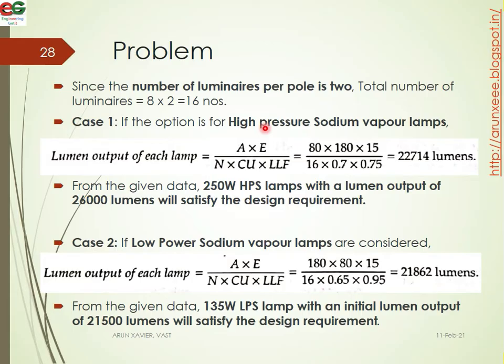The lamp output of each luminaire is calculated using the formula: A times E divided by N times CU. Using area 180 times 80 and illuminance value of 15, with 16 lamps, the required lumen output per lamp works out to approximately 22,714 lumens.